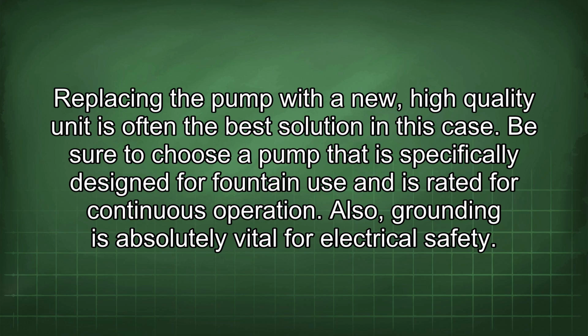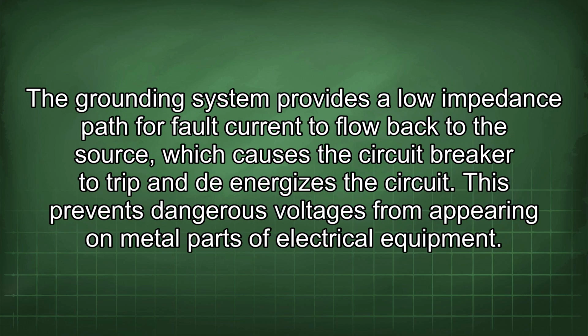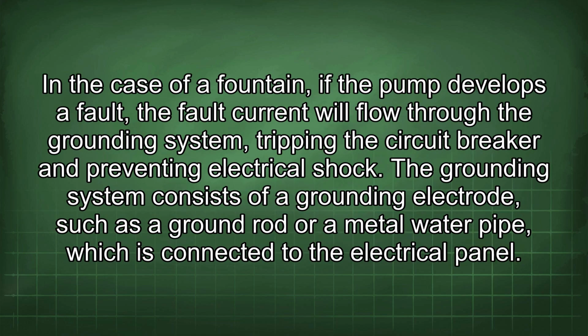Also, grounding is absolutely vital for electrical safety. The grounding system provides a low impedance path for fault current to flow back to the source, which causes the circuit breaker to trip and de-energizes the circuit. This prevents dangerous voltages from appearing on metal parts of electrical equipment. In the case of a fountain, if the pump develops a fault, the fault current will flow through the grounding system, tripping the circuit breaker and preventing electrical shock.